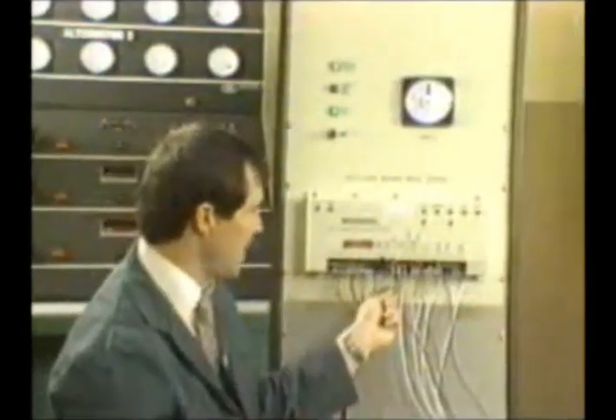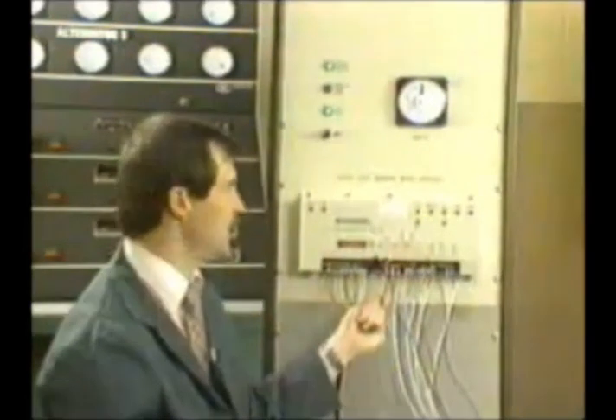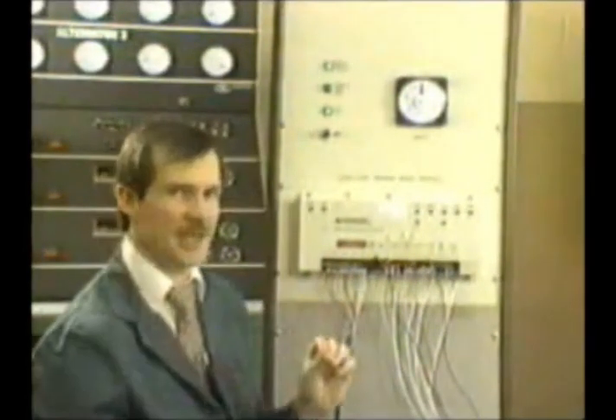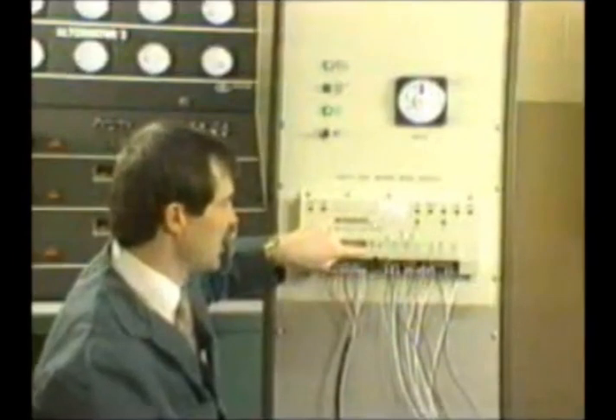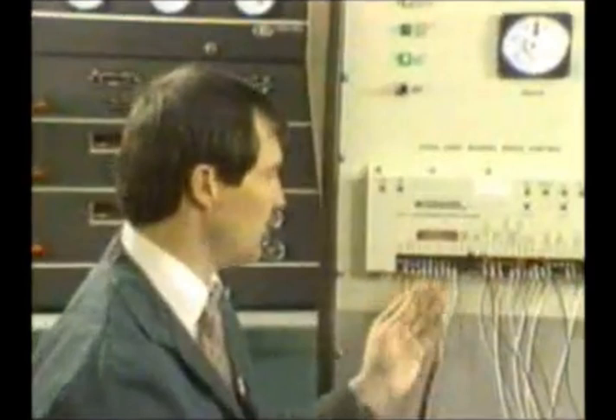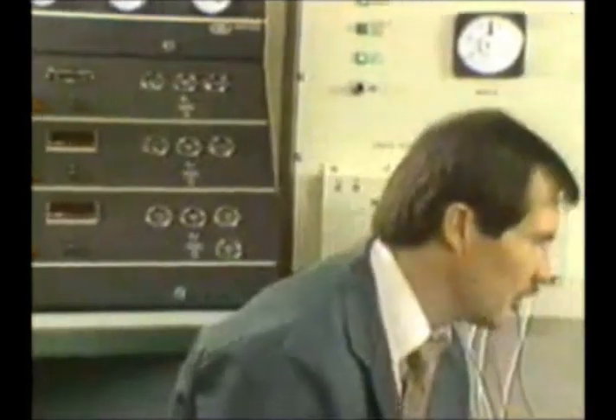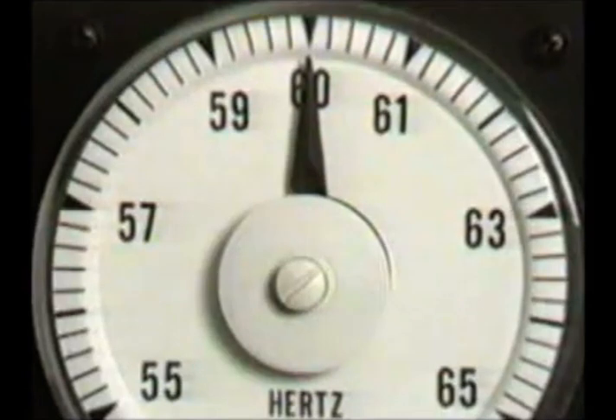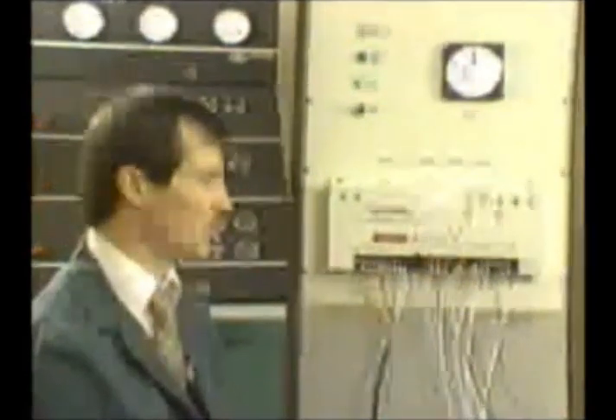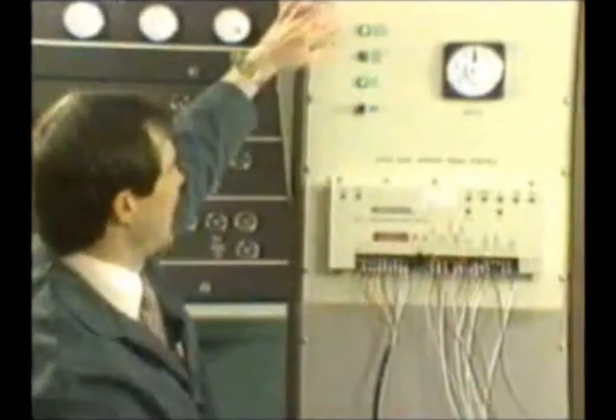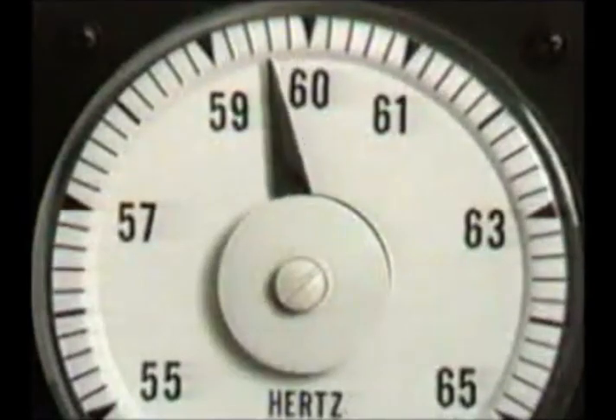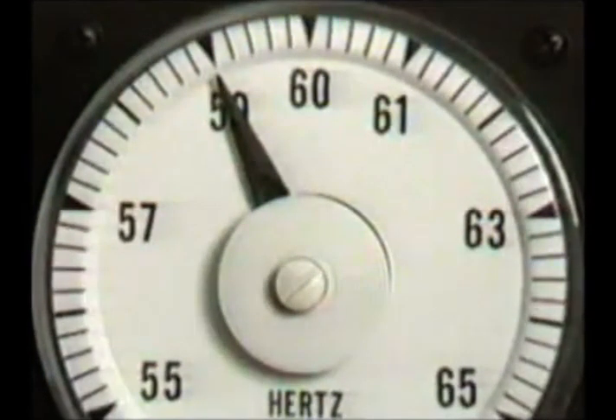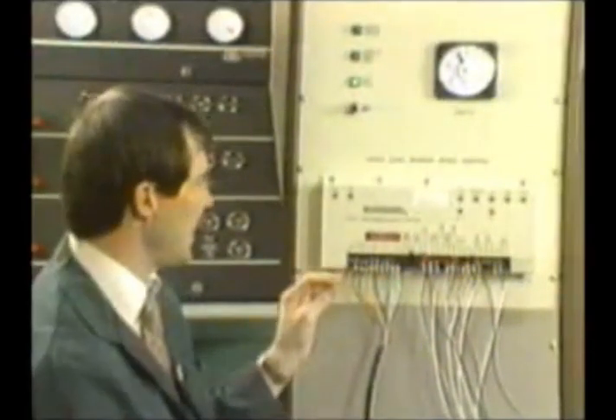You close the breaker, that puts 24 volts on terminal 14. Excuse me. Now we're on isochronous. That relay I was talking about in the load sharing lines is now energized. So if there was another unit online, they could be talking to each other through the load sharing lines. So now let me start loading up the engine. If you watch the Hertz meter, we're going to stay running at 60 Hertz. We're in isochronous now, so we won't droop off. If I open up that circuit breaker auxiliary contact, then we're back into the droop mode. So that's how that functions.